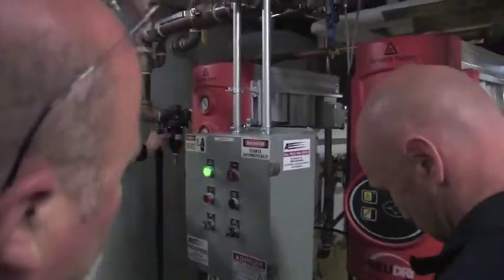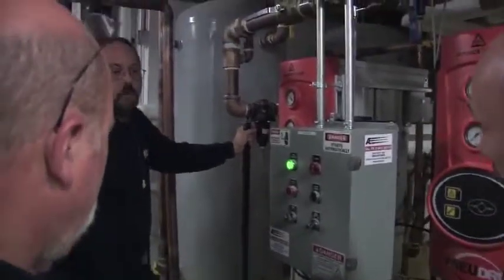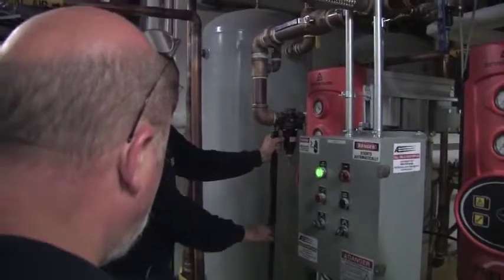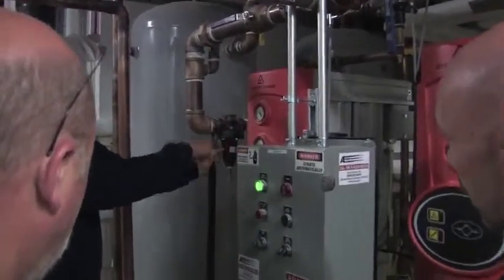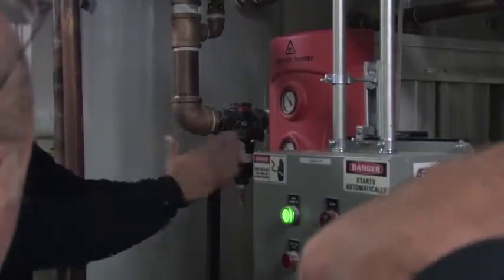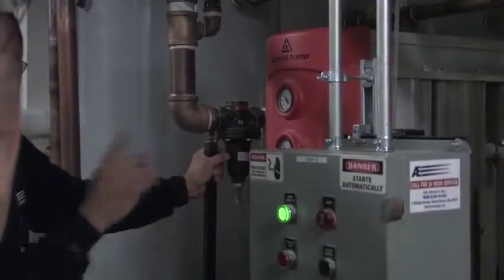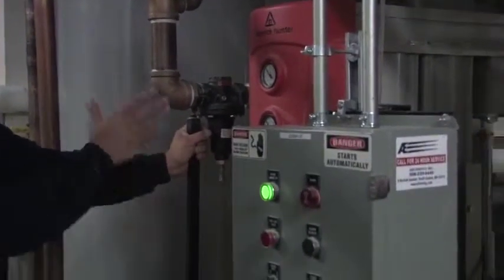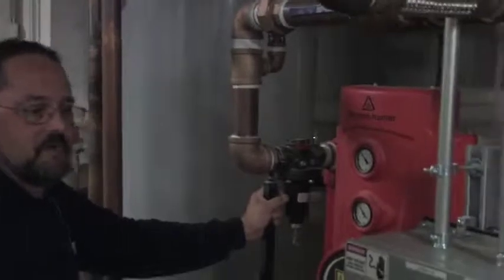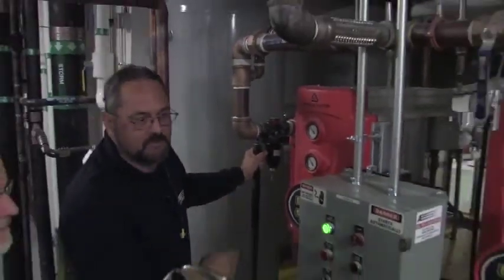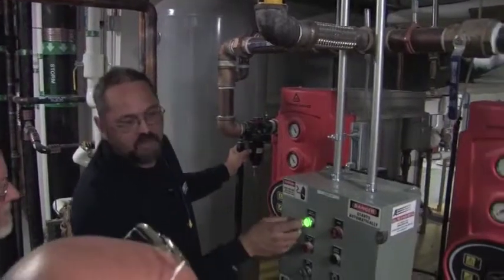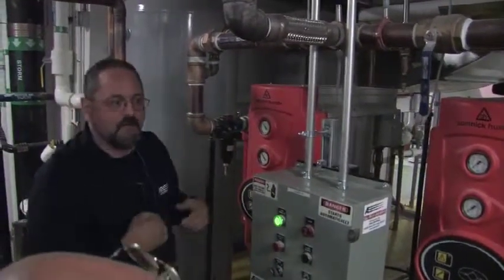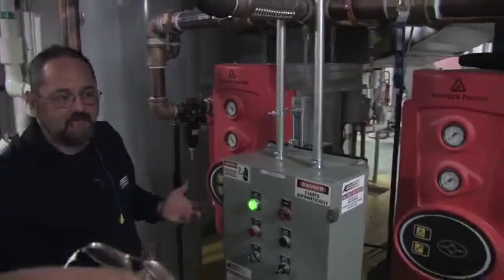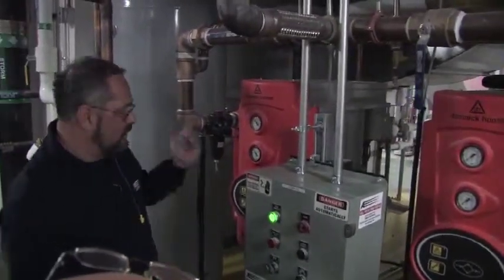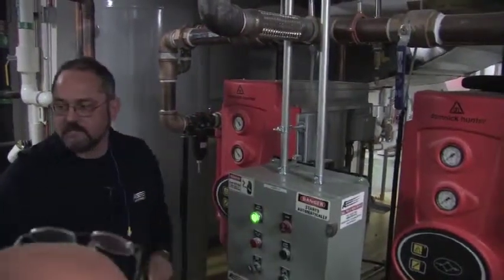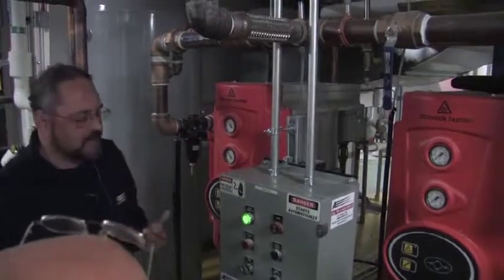The reason they're both pressurized is that our dew point here is minus 20, so we don't need to purge, we're dry enough. It suspends the purging. Internally, it's still switching every 3 minutes which one's online. The same bank doesn't stay online. Left tower's on for 3 minutes, right tower's on for 3 minutes, until the dew point gets high enough that the purge saver goes off, and then it will run a purge cycle. Failing that, if it stays dry enough for 3 days, once every 8 hours it will do 1 cycle just to make sure. That's automatic in the program.